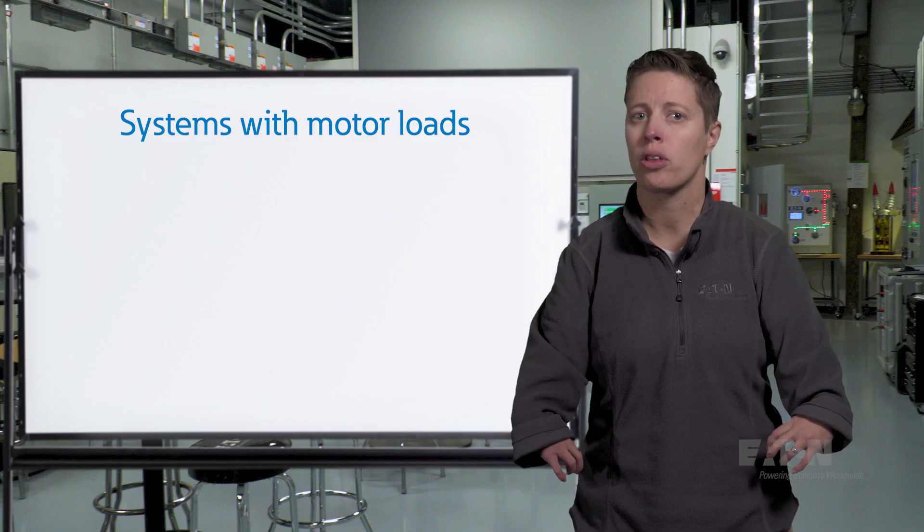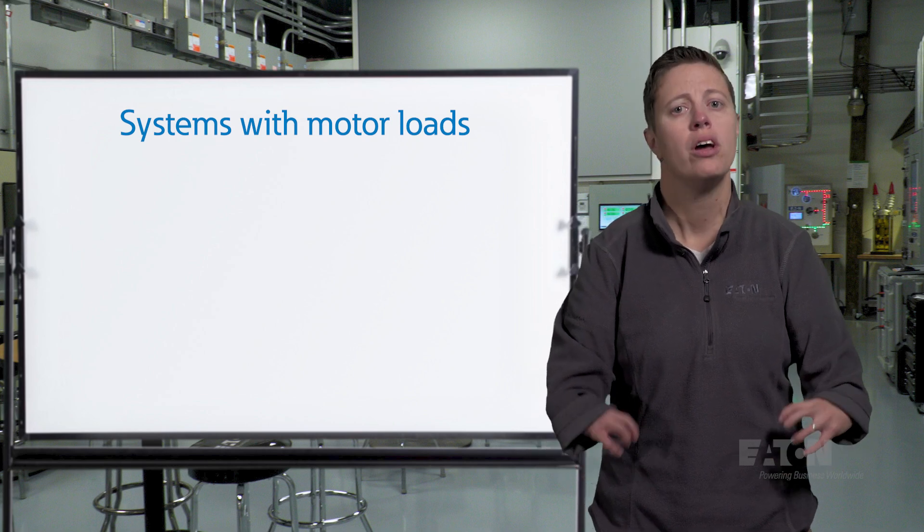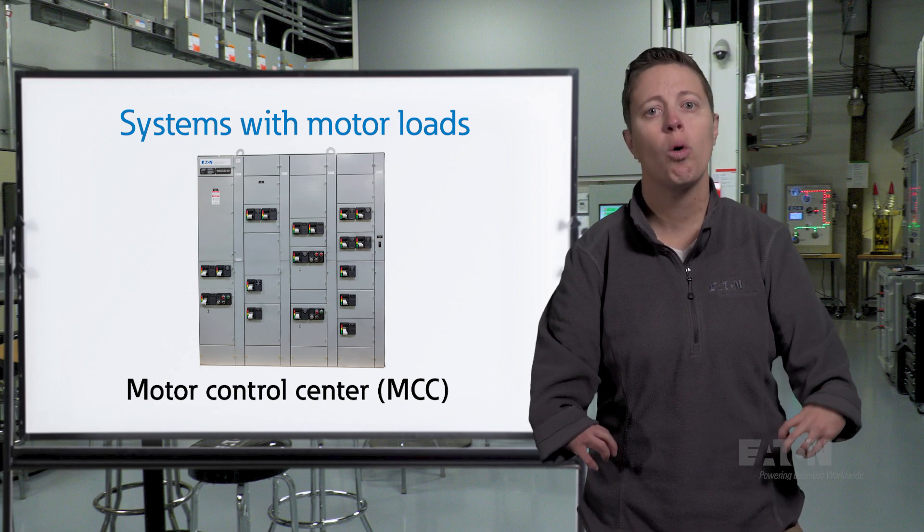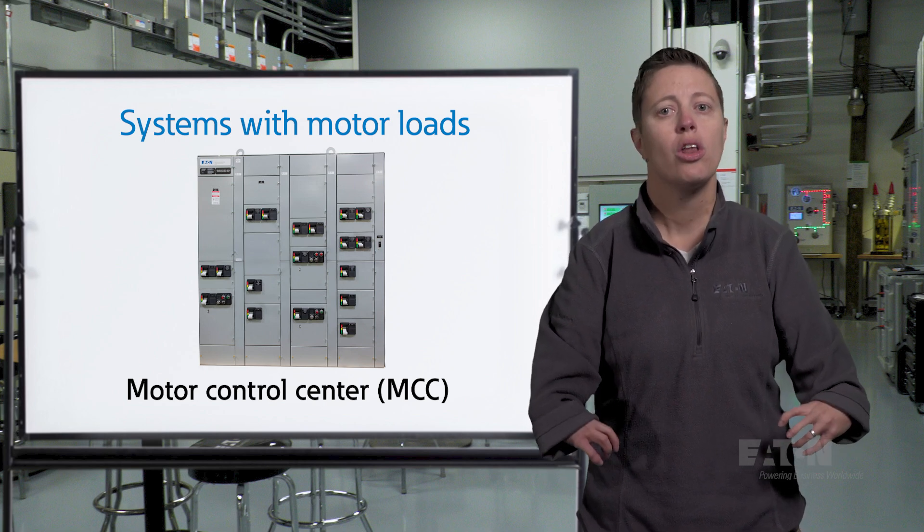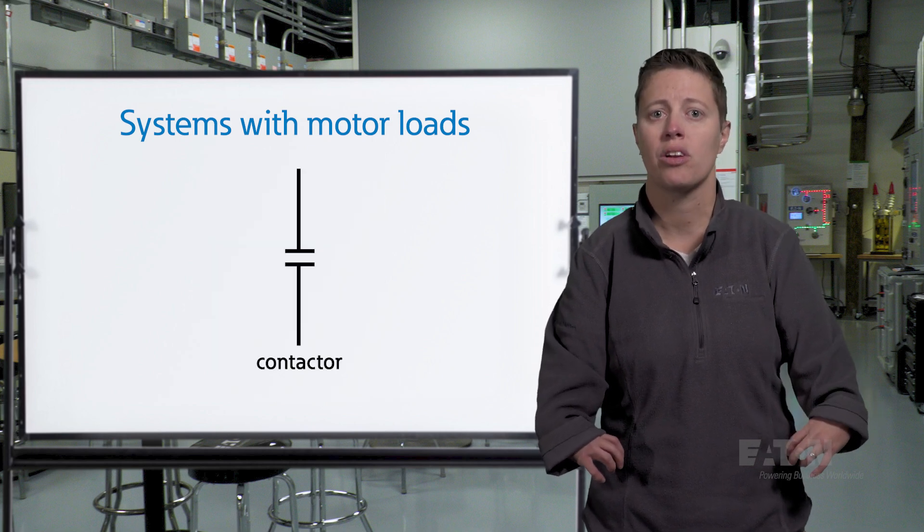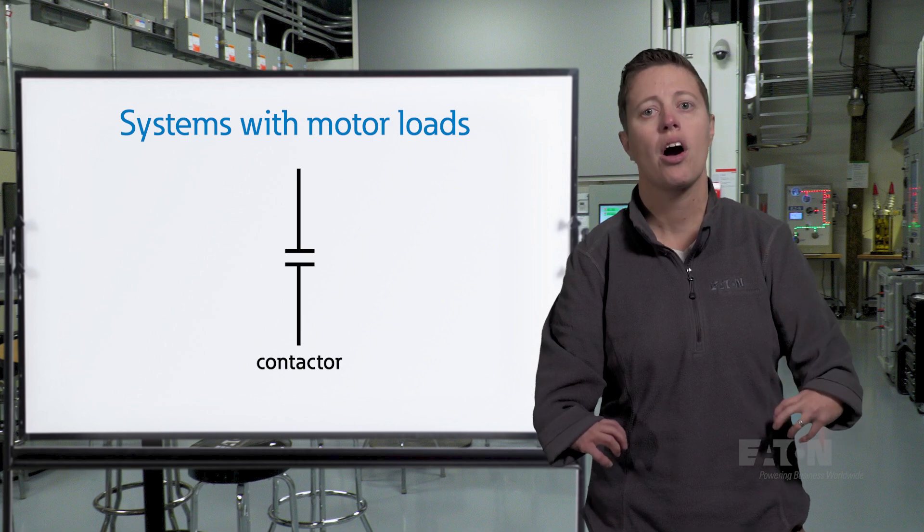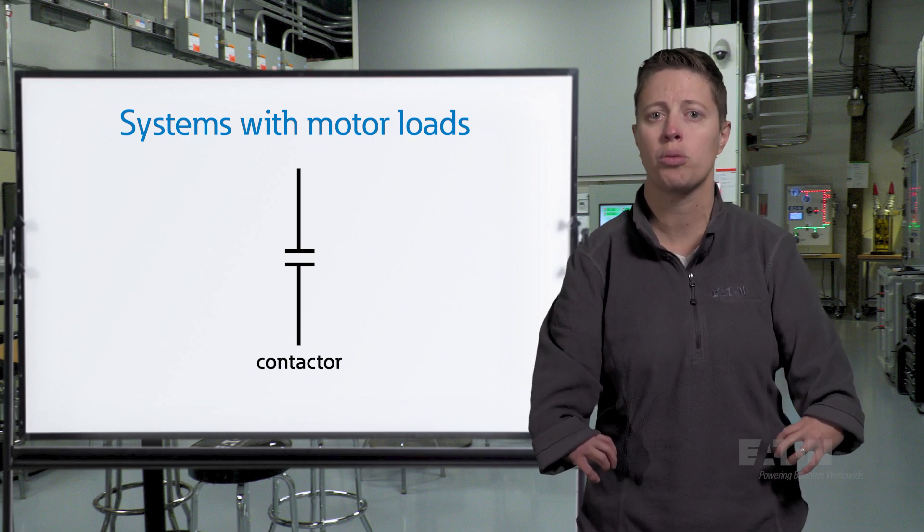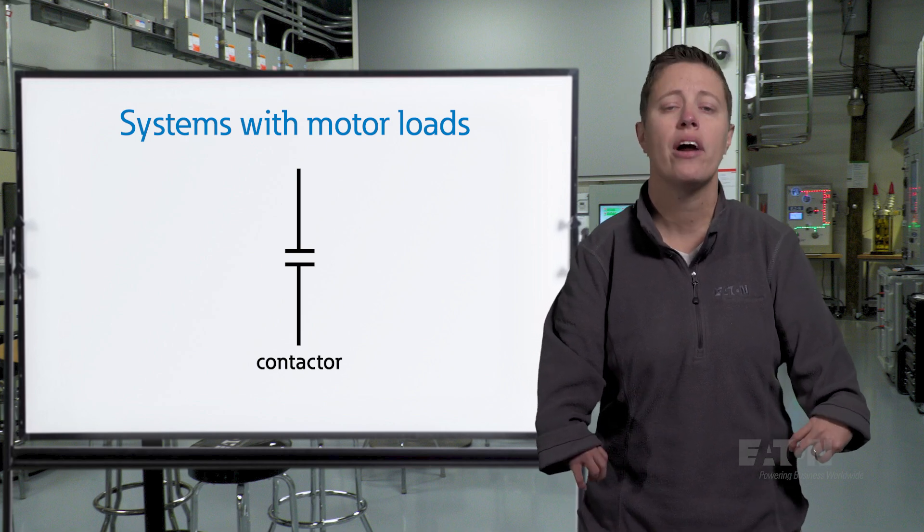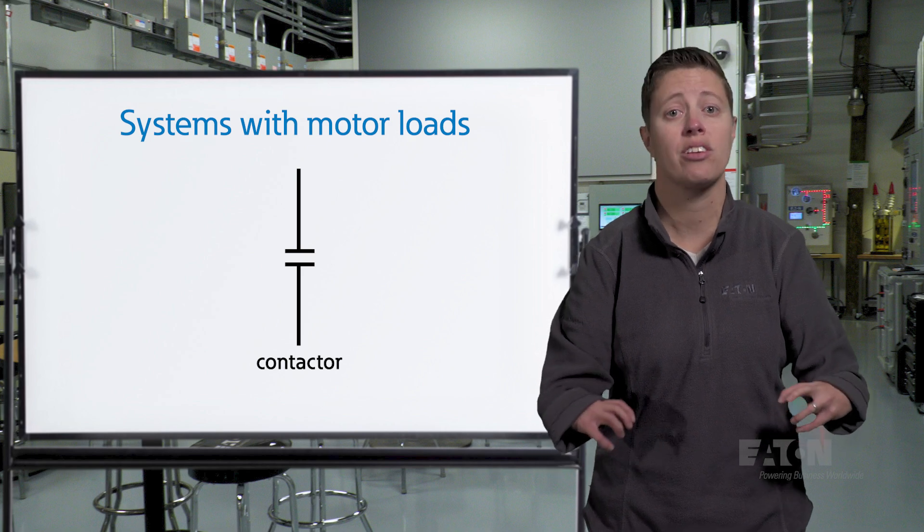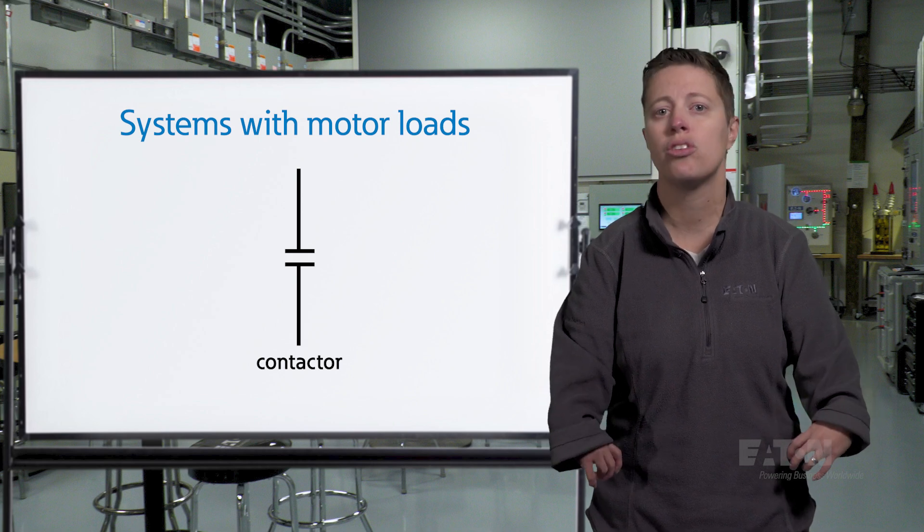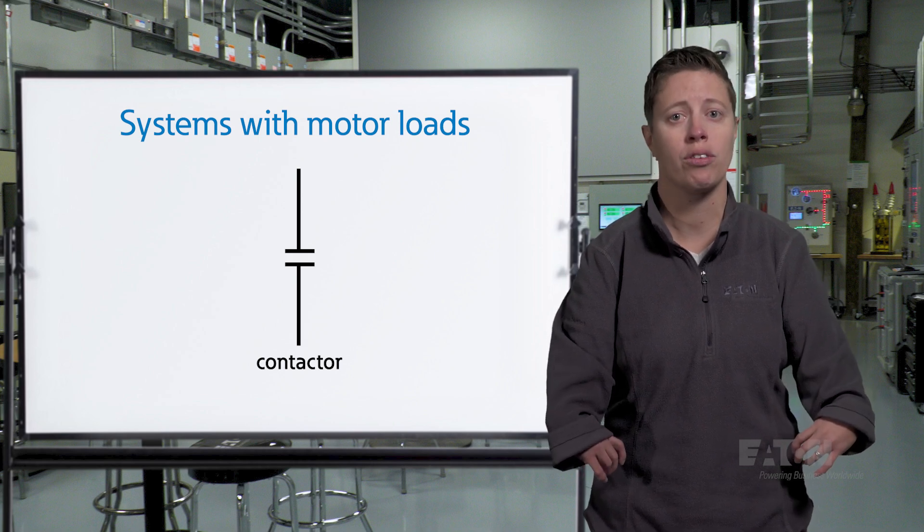Systems with motor loads may use specific equipment to control them, which may reside in a motor control center, often abbreviated MCC, or in a standalone enclosure. Look for these items just upstream of a motor load. Parallel lines perpendicular to the bus represent a contactor. A contactor is a device used to switch an electrical circuit on or off, electrically or mechanically. The parallel lines represent the contactor's contacts in the open position. A contactor can open and close a circuit, but does not provide overcurrent or overload protection.